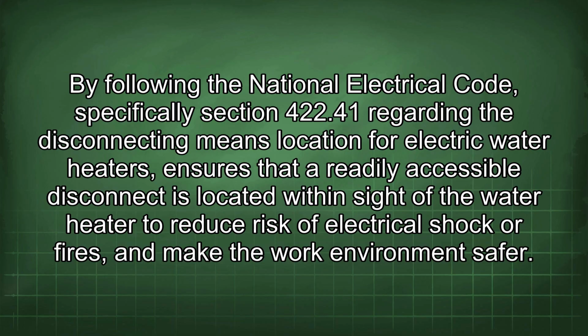By following the National Electrical Code, specifically Section 422.41 regarding the disconnecting means location for electric water heaters, a readily accessible disconnect is located within sight of the water heater to reduce the risk of electrical shock or fires and make the work environment safer.